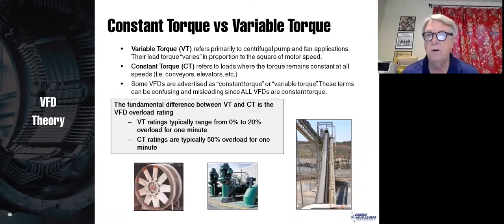Constant torque versus variable torque. There is no such thing in a variable frequency drive. All variable frequency drives are constant torque. The difference is that a variable frequency drive that is listed as variable torque has 110% overload for a minute. A variable frequency drive listed as constant torque has 150% overload for a minute. So both of them are actually constant torque, but if you buy a constant torque drive, you get more overload, and that overload can help you on typically constant torque applications. So a fan or a pump would typically be a variable torque application. 110% overload is fine.